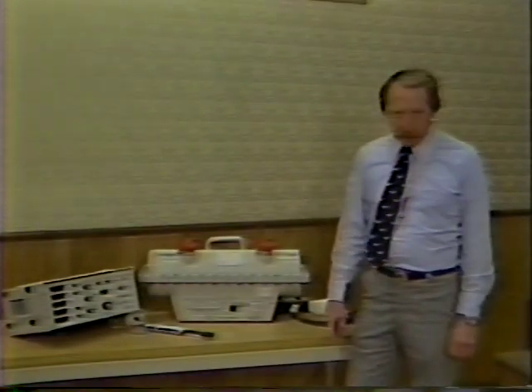Please refer to the next slide. There were 2 changes put into Dynalyzer 3 high voltage unit over that of the Dynalyzer 2. The first is the dual MA range. The second is the anode plus cathode scope output. On the dual MA range, you'll note the switch on the front of the Dynalyzer 3 high voltage unit. In one position, it's fluoro. We're able to read from 0 to 50 MA, primarily for the fluoroscopic readings, and in the rad position from 10 to 2000 MA.